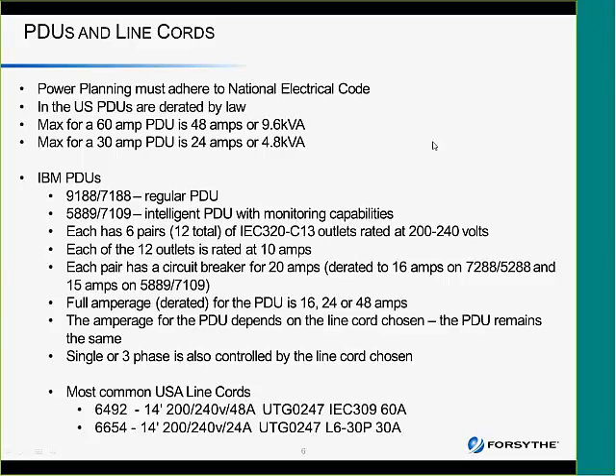In the IBM environment, we have some specific IBM PDUs and line cords, and I'm going to speak to those. But if you're using third-party PDUs and line cords, you can simply translate those. So the first thing is there is a National Electrical Code, and in the U.S., under that National Electrical Code, we are required to derate our PDUs. What does that mean? It means when you think you have a 60-amp PDU, well, first of all, the PDUs are actually all identical. They can be 30, 60, or I think 120 amps. It depends on the line cord.